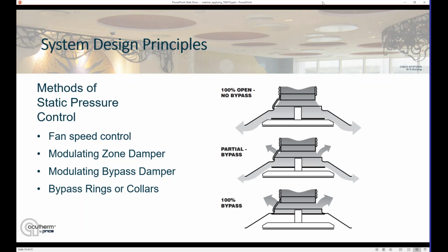Another option for a bypass is a relief ring or a relief collar. These are devices that create a bypass right on the diffuser. Now as the pressure at that individual diffuser starts to increase, air then gets bypassed into the ceiling. And these do require a ceiling plenum return system to operate, but they can be a very economical way to get a bypass into a constant volume system. A good option in some of those retrofit situations where there's no plan to ever put a VFD on the fan.